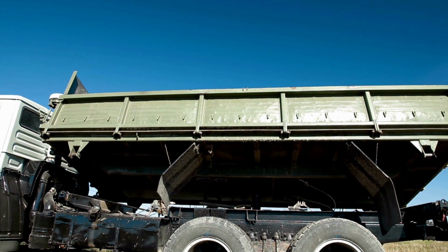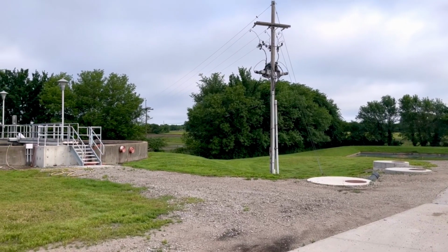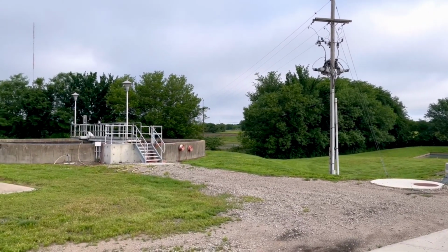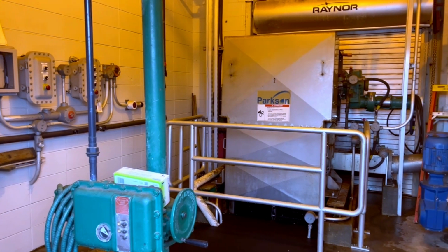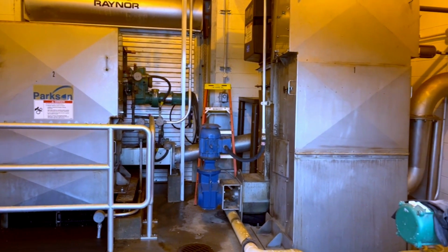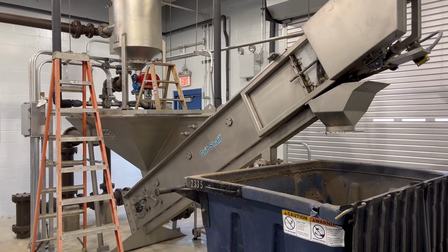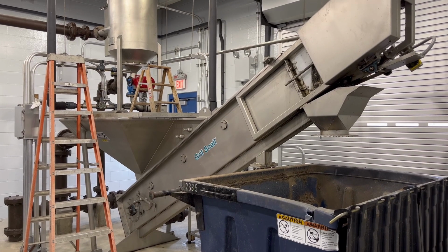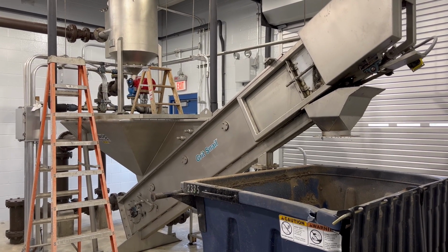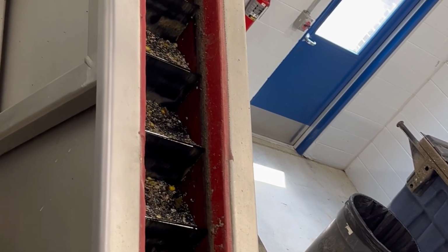After being screened, the water flows into a wet well, an in-ground holding tank, and 4 pumps are used to send the water to the head cell. During this part of the process, the plant is removing fine material that was too small to be removed by the initial screens. This stops small debris from entering the plant and settling to the bottom of the basins. The fine material goes through a machine that separates the material from water. The water then returns to the head of the influent building.